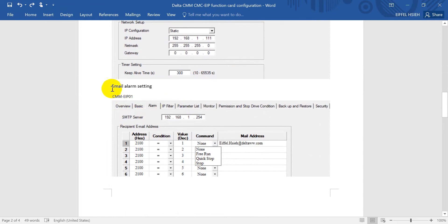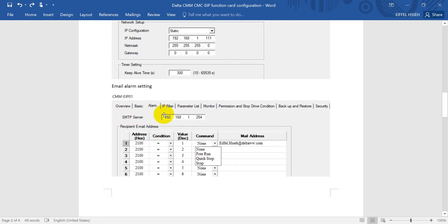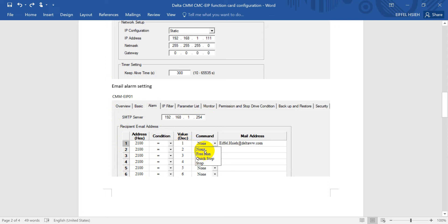Another one is for the email alarm setting. So basically if you want to use this function, you must connect to the SMTP server. That means you can send out an email, and then you can set the condition, example like error code equal to certain value, and you can define the command as free run, quick stop, or stop, and then you can set up the email address.